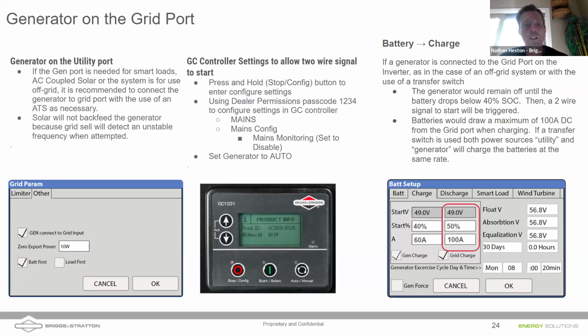Additionally, there's a priority setting at the bottom, and one of them says battery first and the other says load first. That's where your priority setting is for that generator power. So if you choose battery first, it will make sure that it uses the power of the generator to meet your battery charging set points. So if you say, on the right side of the screen, 60 amps of DC power goes directly to battery charging, it does that before it covers the loads of the house.